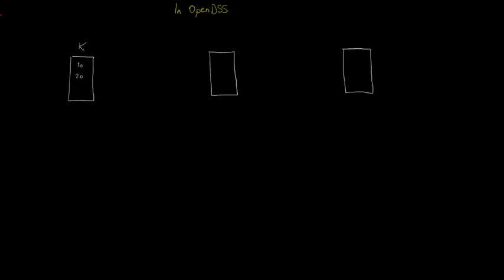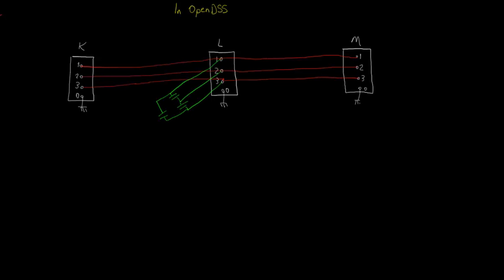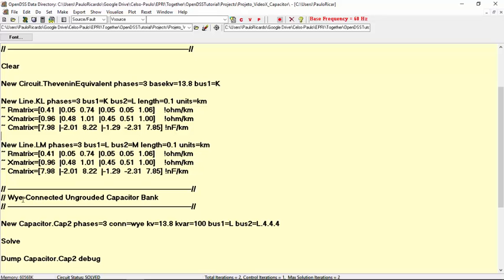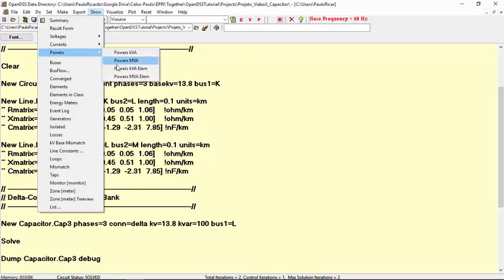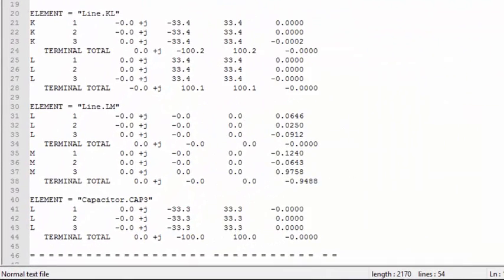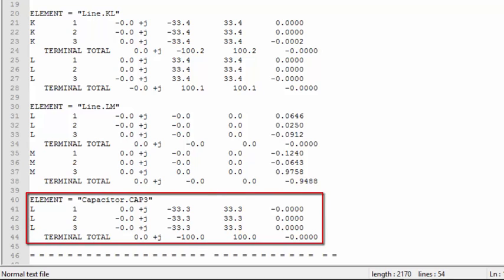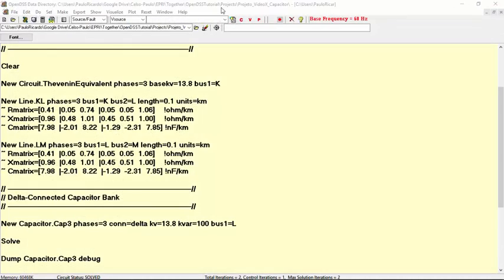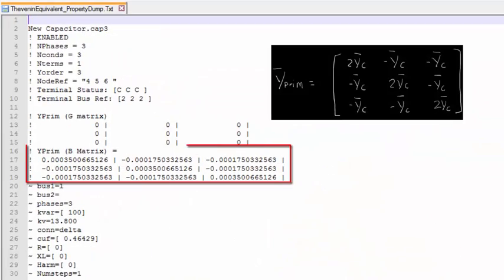In OpenDSS, this is the new situation. The code is essentially the same as we used in the first case. We just need to switch the connection from Y to delta. There is no need to define the second bus. Solving the circuit, we can verify that the reactive power absorbed by the three-phase delta-connected capacitor bank is 100 kVAR, as expected. Keep in mind that this is only true because the voltage across the capacitor bank is nearly the rated voltage; otherwise, the power absorbed would be different, as the capacitor bank is modeled as a constant impedance, not a constant power. Running the dump command, we can see that the Y-primitive matrix is exactly what we expected. Notice that for a delta connection, there is no second terminal, which is why the matrix order truly matches the matrix we have derived.